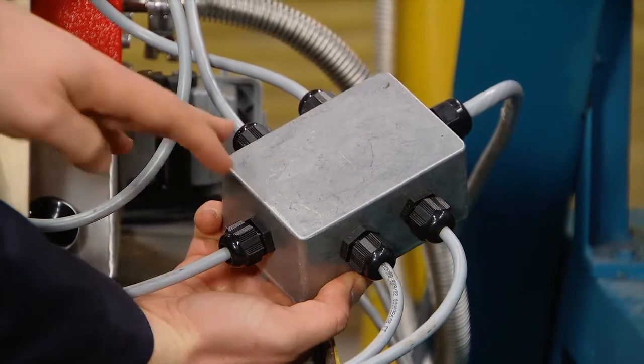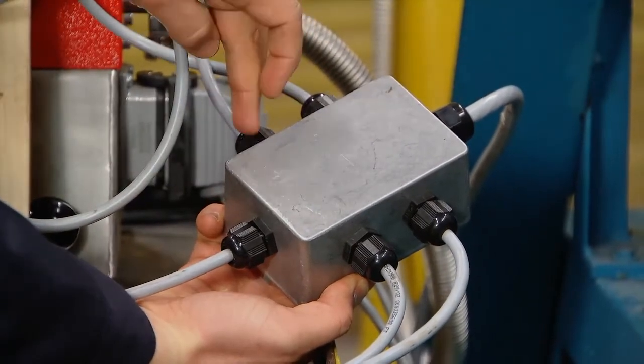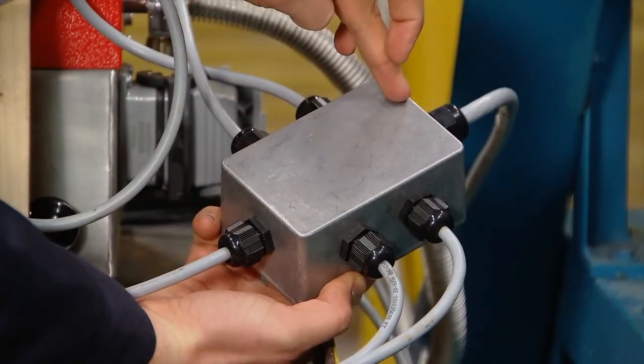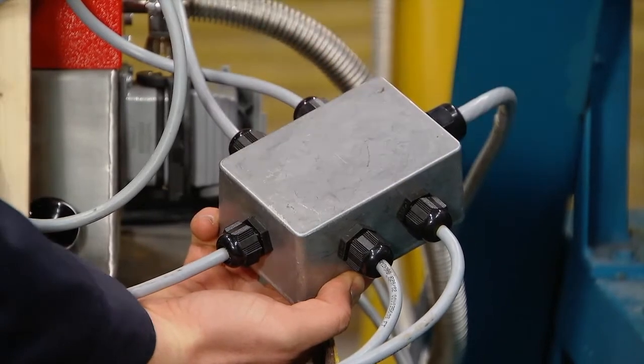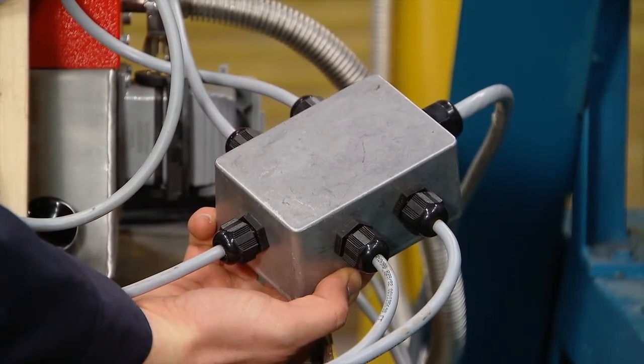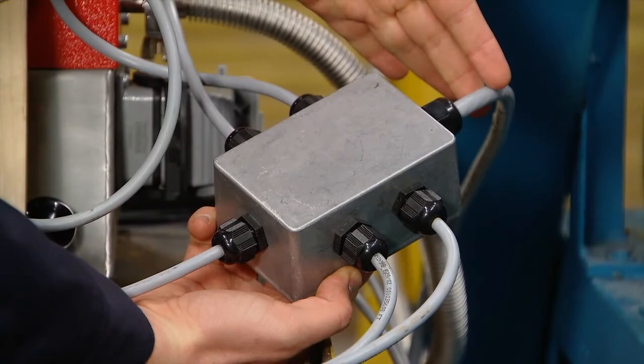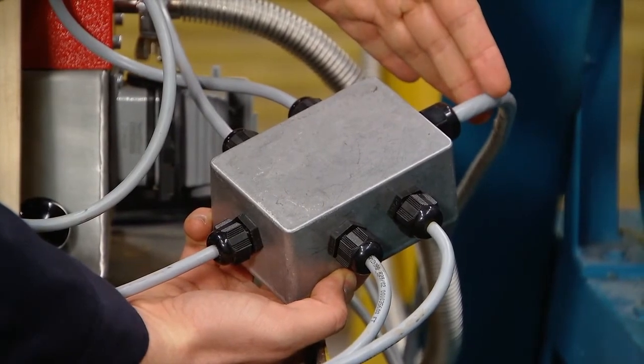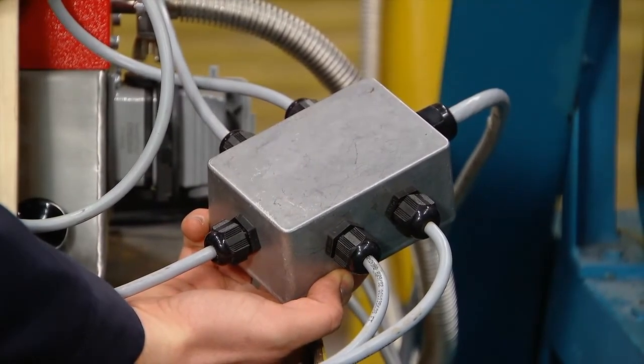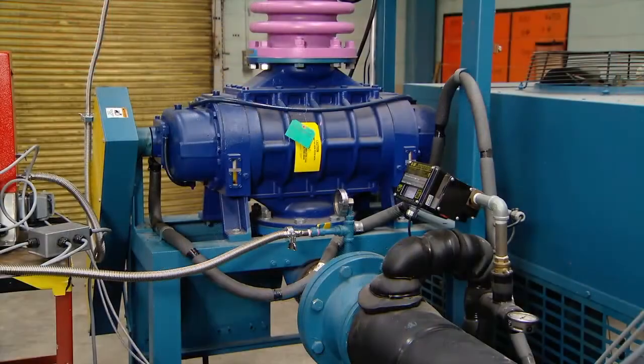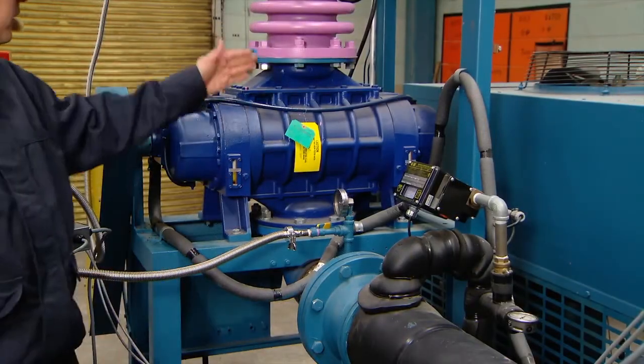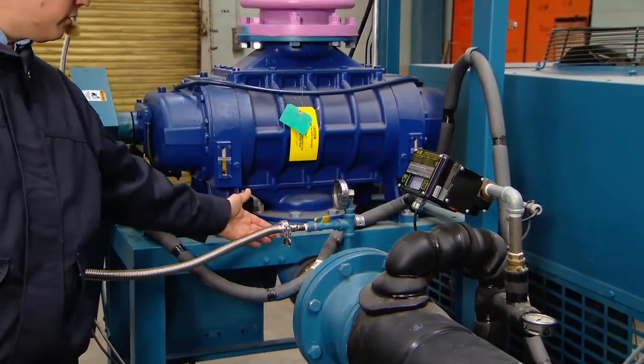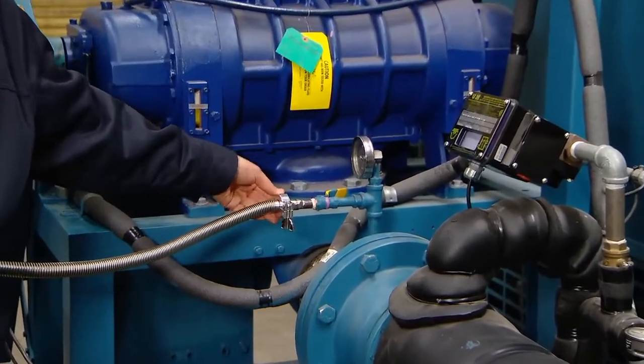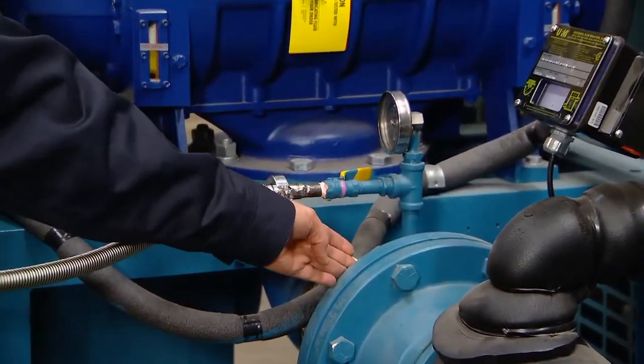This is a split box with the 5 inputs, 1, 2, 3, 4, 5, where a cable goes to the magnetic valves on the VZ475. The 6th cable is a main cable going to the control cabinet. The vacuum connection for the VZ475 should be after the booster, the roots pump, and directly connected to the main vacuum line.